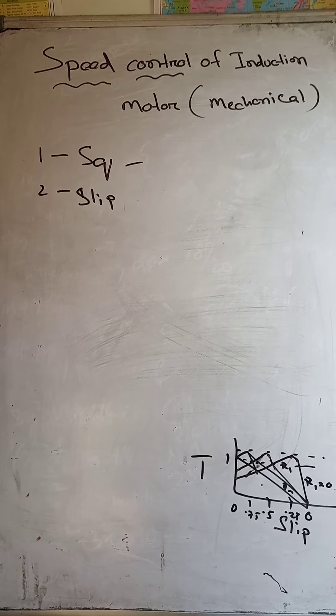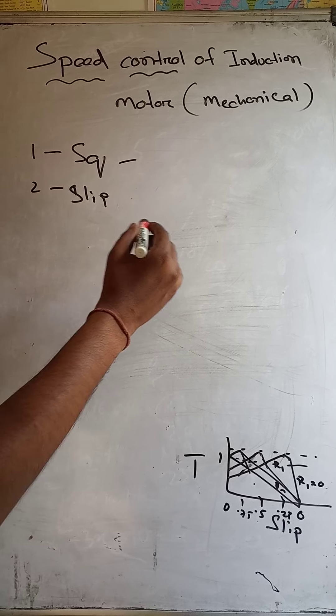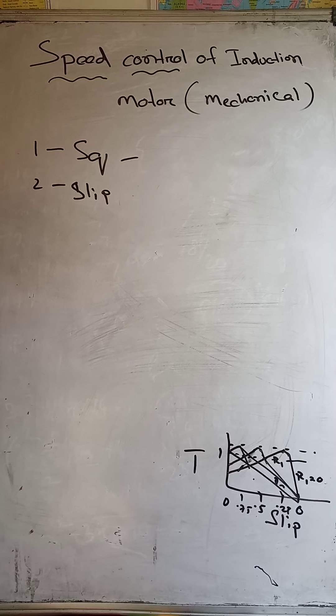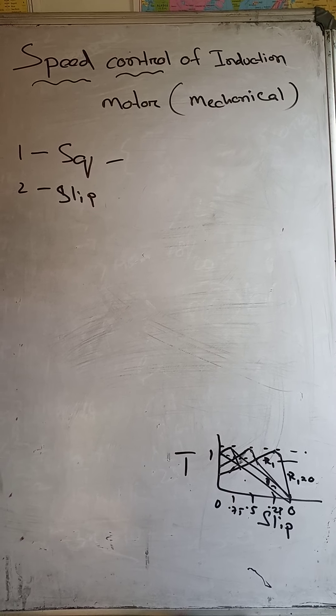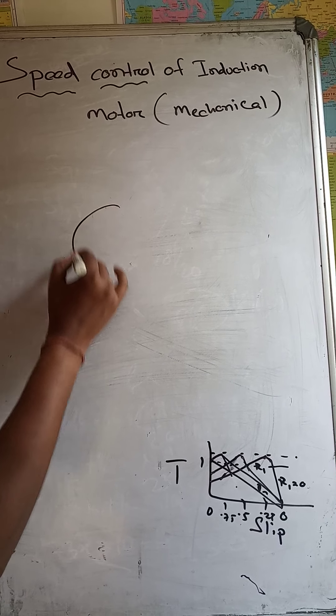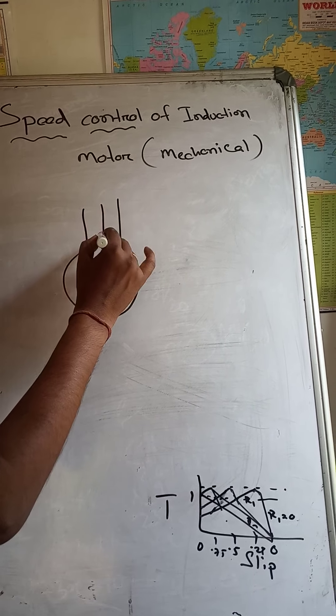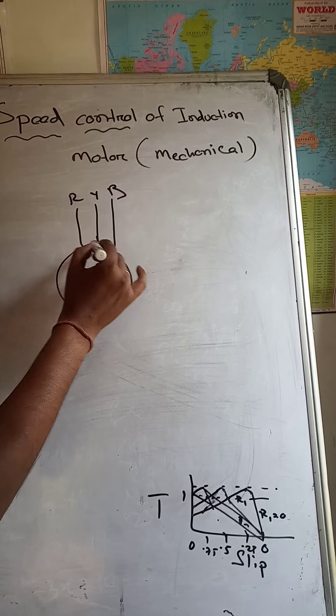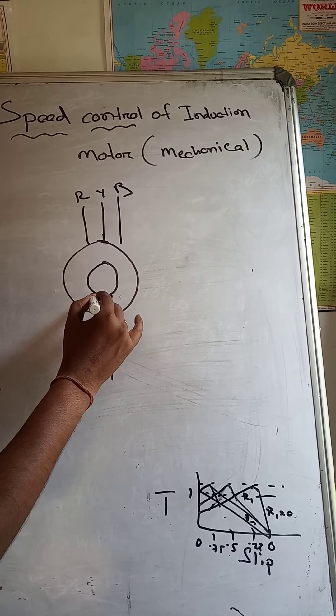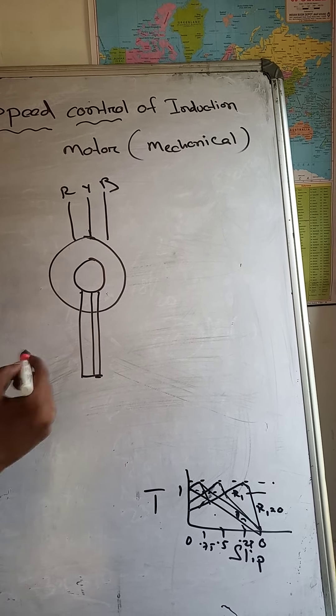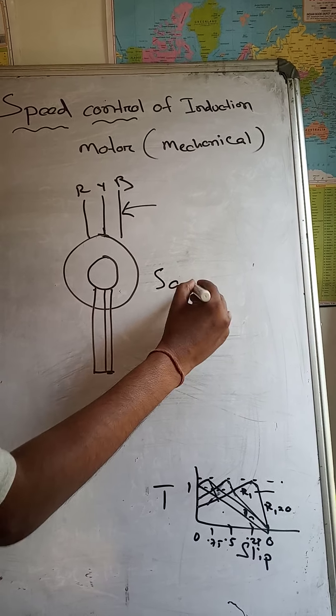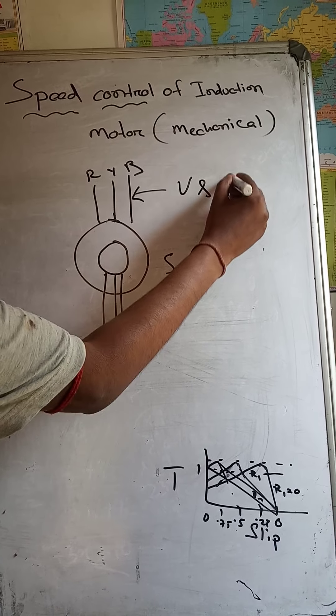In a squirrel cage induction motor, the rotor is short-circuited. That's why you cannot change the speed with respect to resistance. We can change the speed of a squirrel cage induction motor by changing the frequency and the voltage. If you see, this is the stator and this is the rotor — if you give the three-phase supply R, Y, and B to the stator, the rotor is short-circuited.